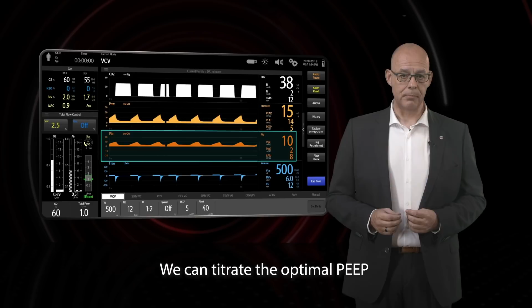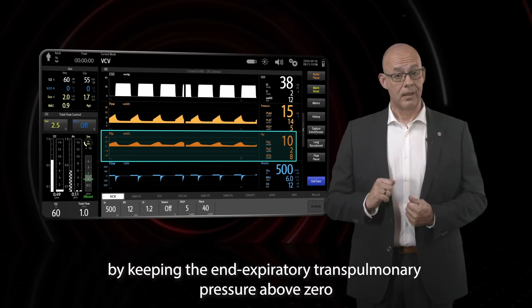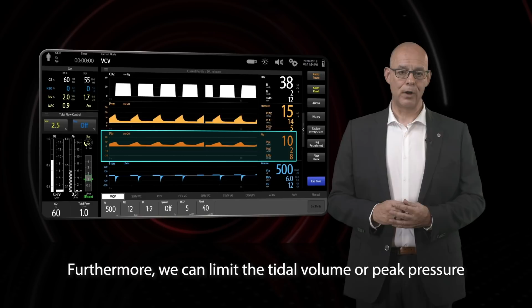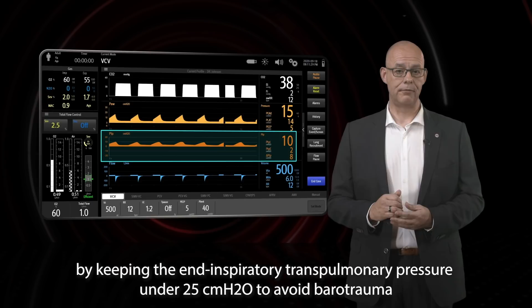We can titrate the optimal PEEP by keeping the end expiratory transpulmonary pressure above 0. This is to avoid alveolar collapse. Furthermore, we can limit the tidal volume or peak pressure by keeping the end inspiratory transpulmonary pressure under 25 centimeters of water to avoid barotrauma.